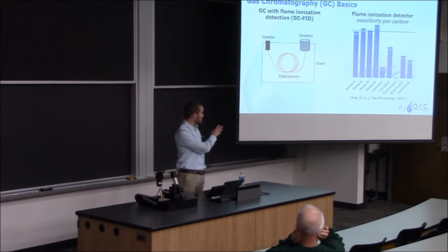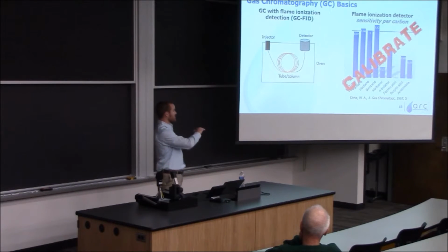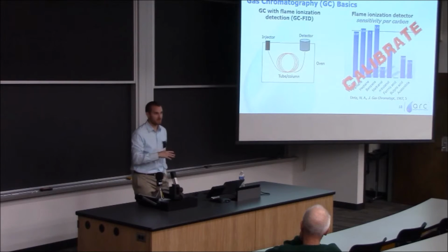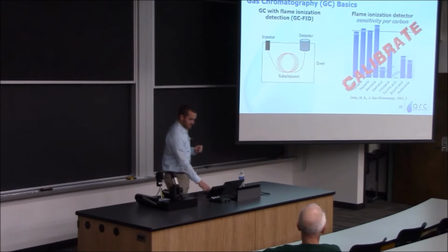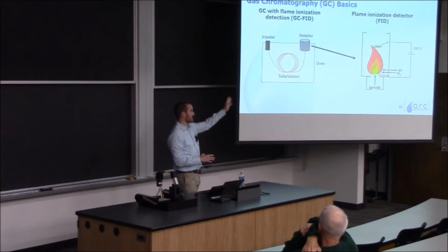So in order to study these compounds, you need to calibrate the FID. And these response factors can actually change depending on which FID you're using, because inside of this flame you're actually doing hydrogenolysis reactions. And those hydrogenolysis reactions that split the molecules depend on the temperature, the hydrogen, the air that's in there. So you need to calibrate your FID before each experiment.